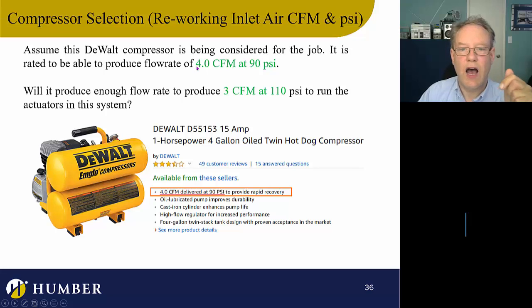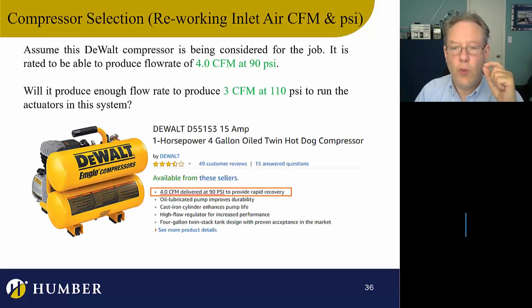To do the math we must convert the pressures to PSIA — that's the first thing. We've got 90 PSI and 110 PSI gauge. Adding 14.7 to each converts them to absolute. Using the gas law, we add time to both sides of the formula and get volume over time, which is flow rate. So P₁ × Q₁ = P₂ × Q₂, and we throw those numbers in.